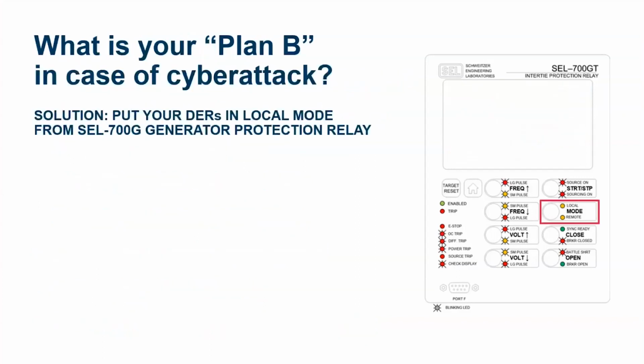Something we need to point out, cybersecurity doesn't have to be complicated. In many cases, the ability to simply turn off a remote algorithm, a cloud-based system, can be your plan B. If you don't have a plan B, use a relay to be your plan B. In this case, by walking to the front panel of this relay, pressing the button to go to local, it immediately cuts off all communication and all controls from any remote system, either the local SEL microgrid controller or a SCADA interface, a DERM system, an ADMS. It shuts it off. This is gorgeous. This allows you to have a plan B, a technician in a truck with a radio, drive to the job site, put it in local, and you don't lose power. That is a simple cybersecurity plan B.